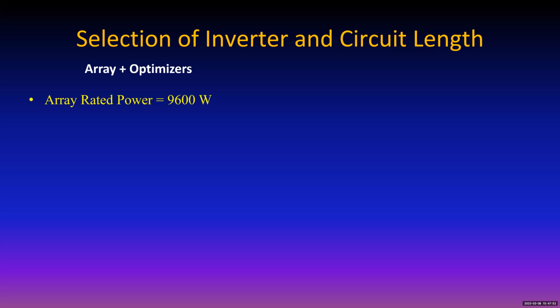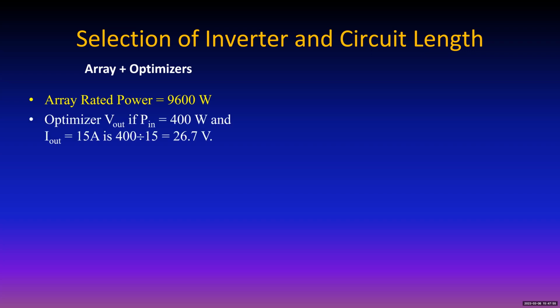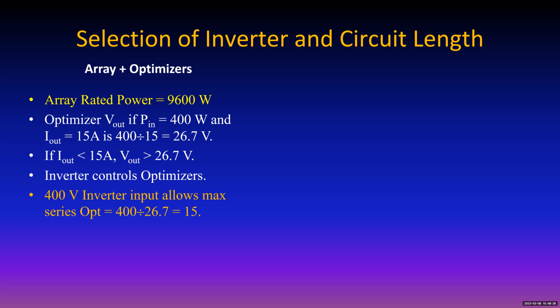So the array plus the optimizers, you're looking at 9,600 watts. So if the input power is 400 watts for the optimizer, and the output maximum can be 15 amps, then that would be a voltage of 26.7 volts. And so that's how low the voltage might go with full output current. All right. And so the output is more than 26.7, and if the output current is less than 15 amps, then with the same input power, if the current goes down, the voltage has to go up. Very simple. The inverter does the controlling of these optimizers.